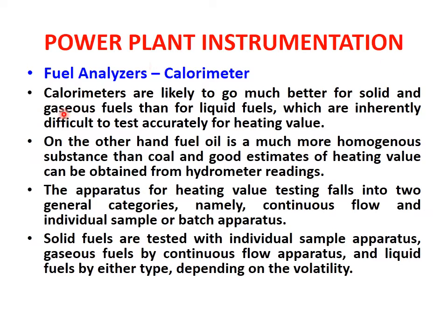through the measurement of the temperature of the exhaust gases, the calorific value can be related. Calorimeters are likely to do much better for solid and gaseous fuels than for liquid fuels, which are inherently difficult to test accurately for heating values. Because for solid and gaseous fuels it is much easier to measure, but liquid fuels are composed of various chemicals, so it is harder to accurately measure the heating value, that is, the calorific value.